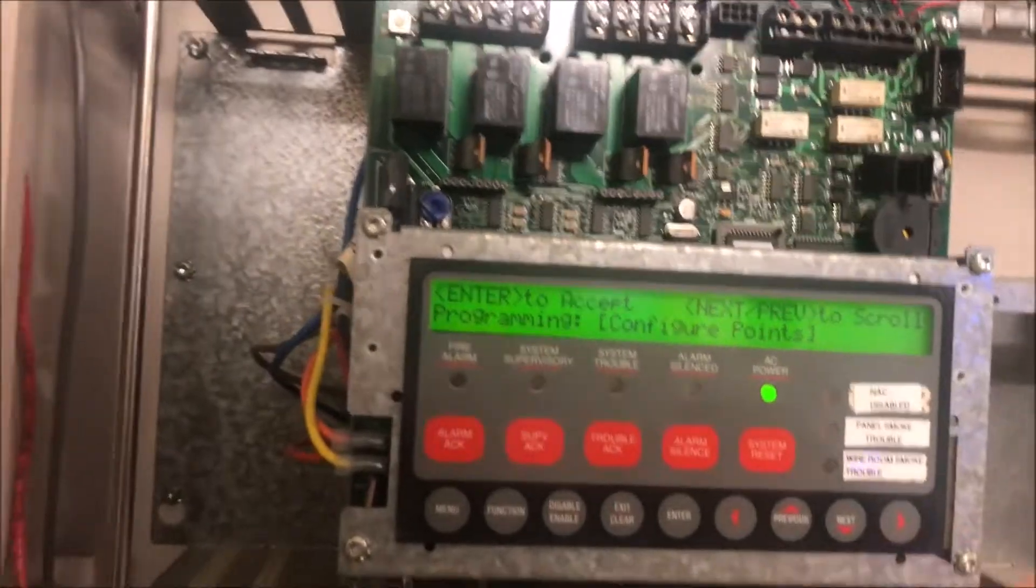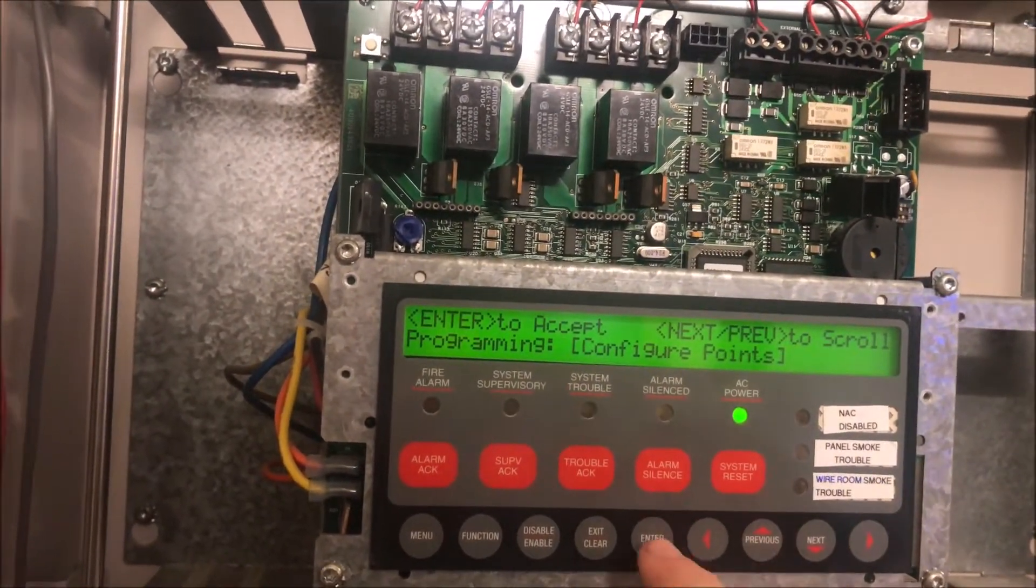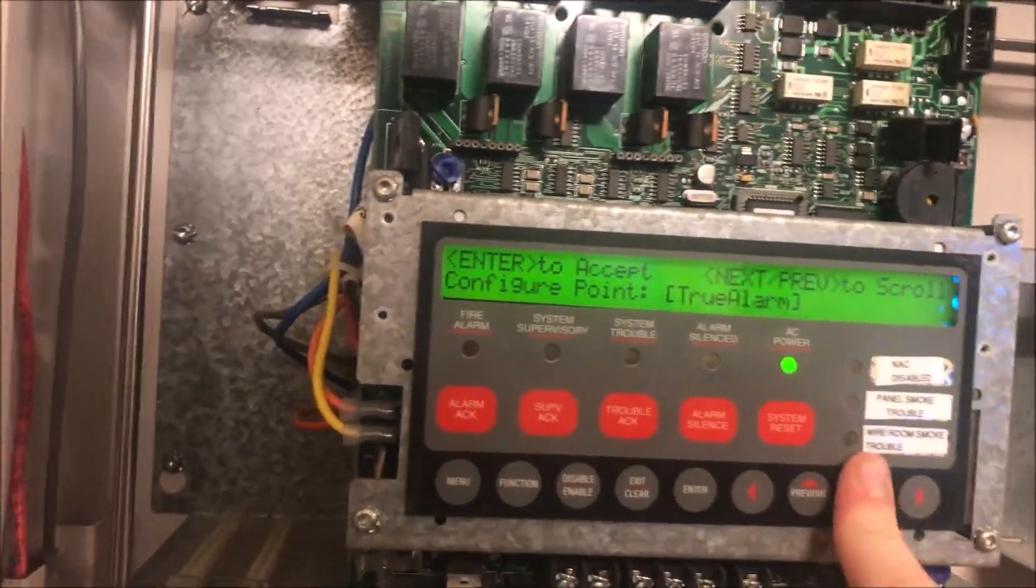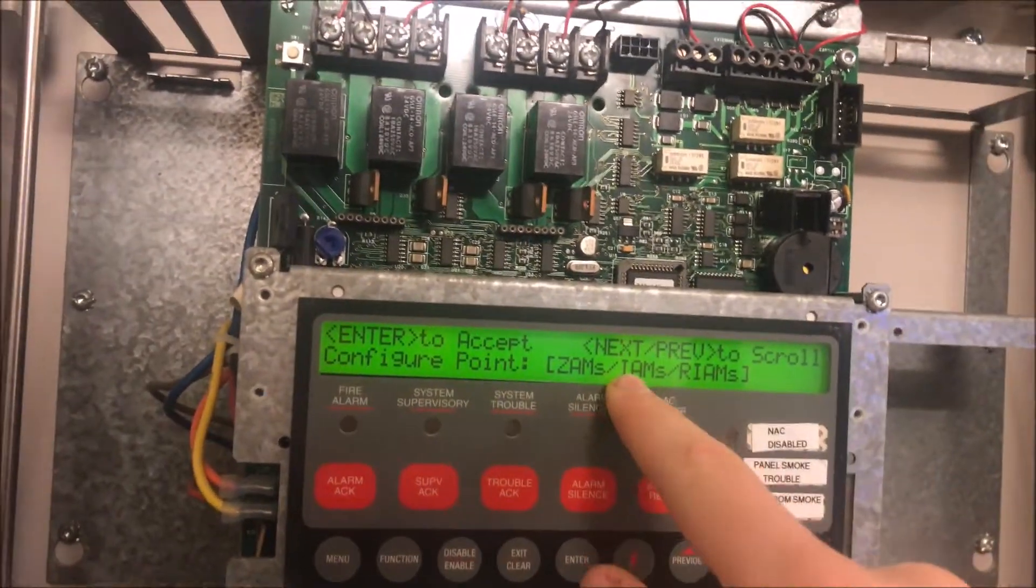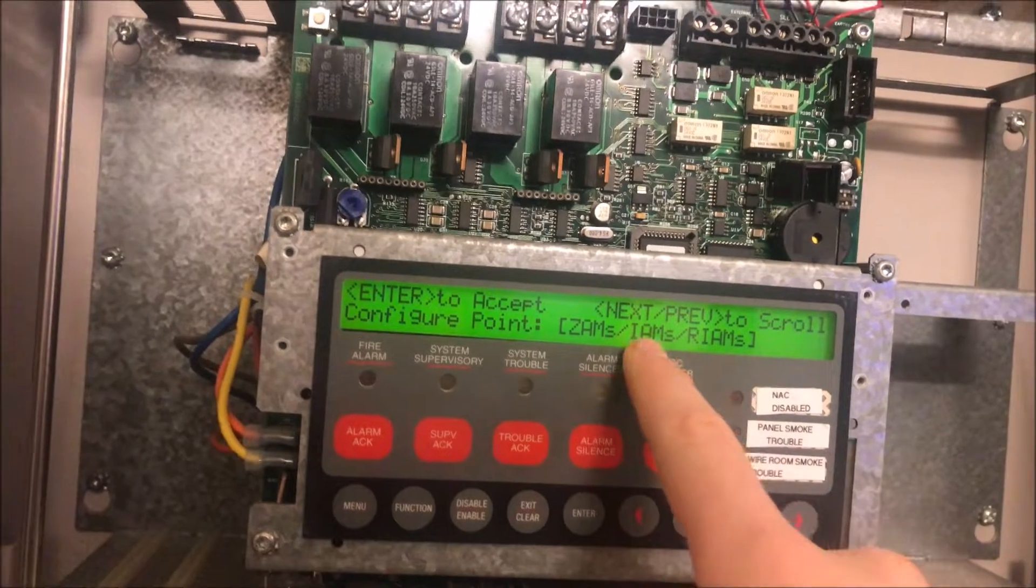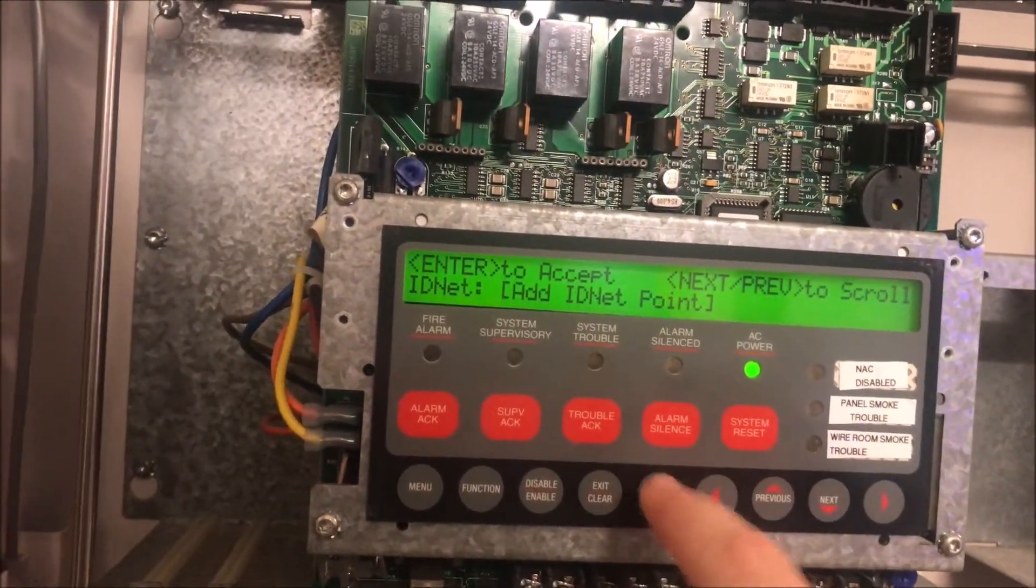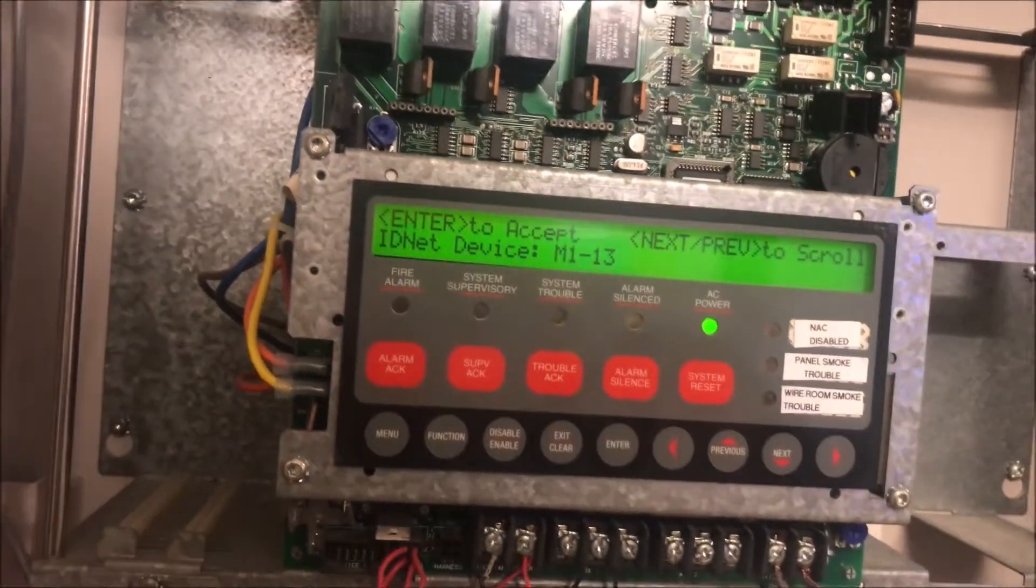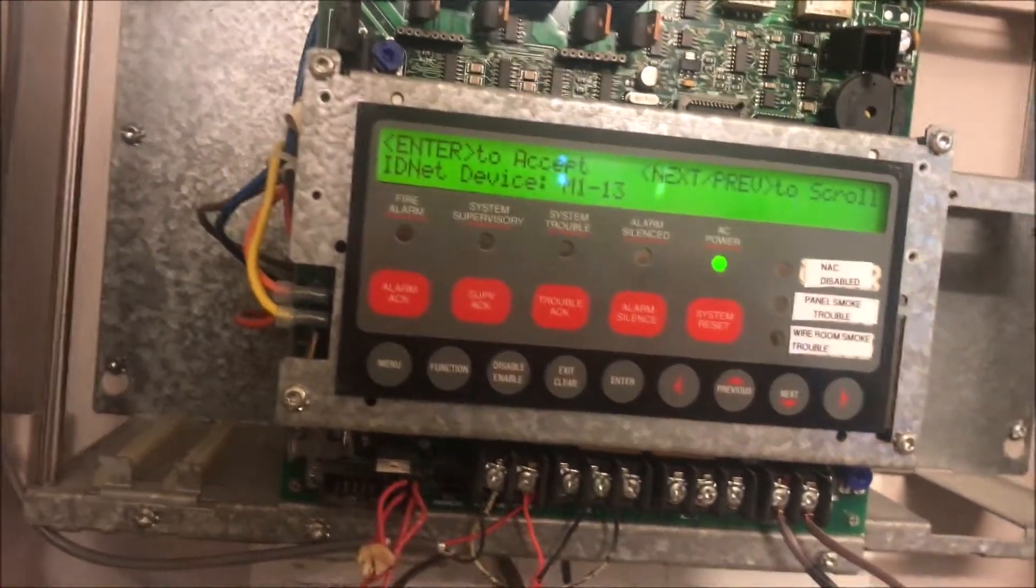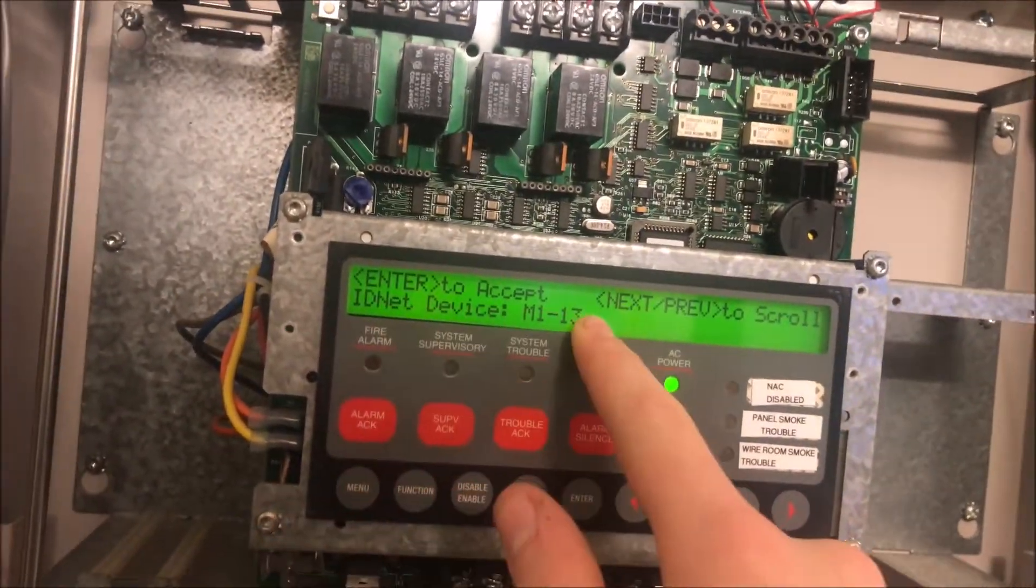So we are going to go into configure points, hit enter, and go to our IAM, because the pull station we are working on is an IAM. We're going to hit enter, add IDnet point. This is the first way you can do this - if you're adding one or two points. IDnet device M113.